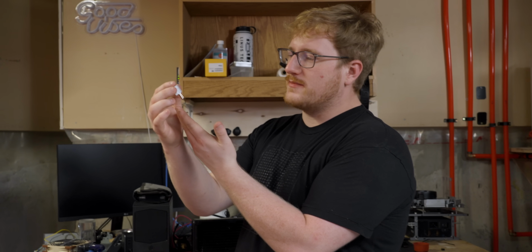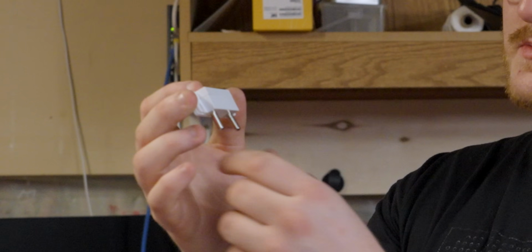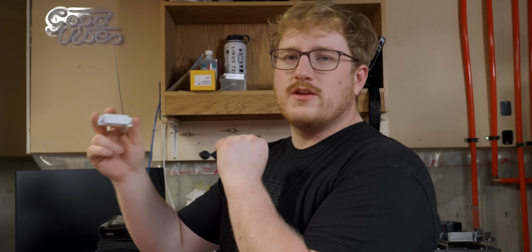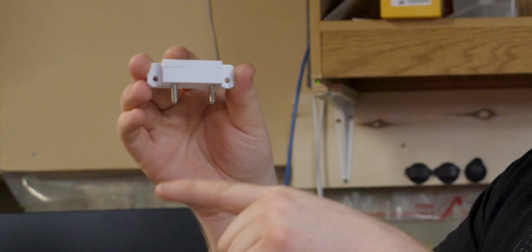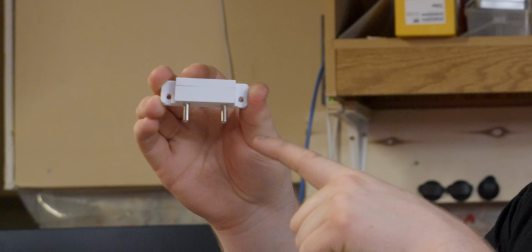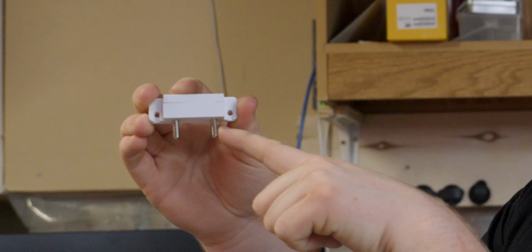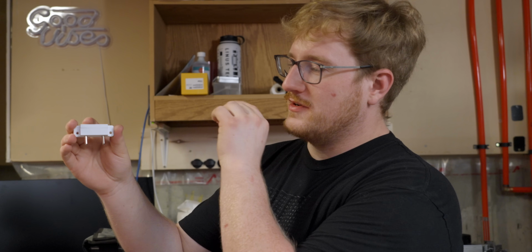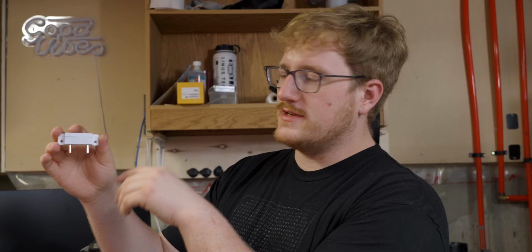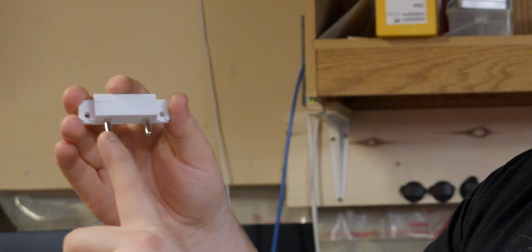While Reese works on getting all the systems grounded, let's talk sensors. We have 3 different types, starting with our leak sensor, although calling it a sensor might be a bit generous. This is basically just 2 wires. You apply voltage to one side, and as your leak bridges the gap with water, it creates an electrical connection between the other side, and on that side, you're just sensing for any voltage. So when there's no water, it should be 0 volts-ish, and when there is water, let's say if we did 5 volts on this side, it'll probably show like 1 or 2 volts on this side.